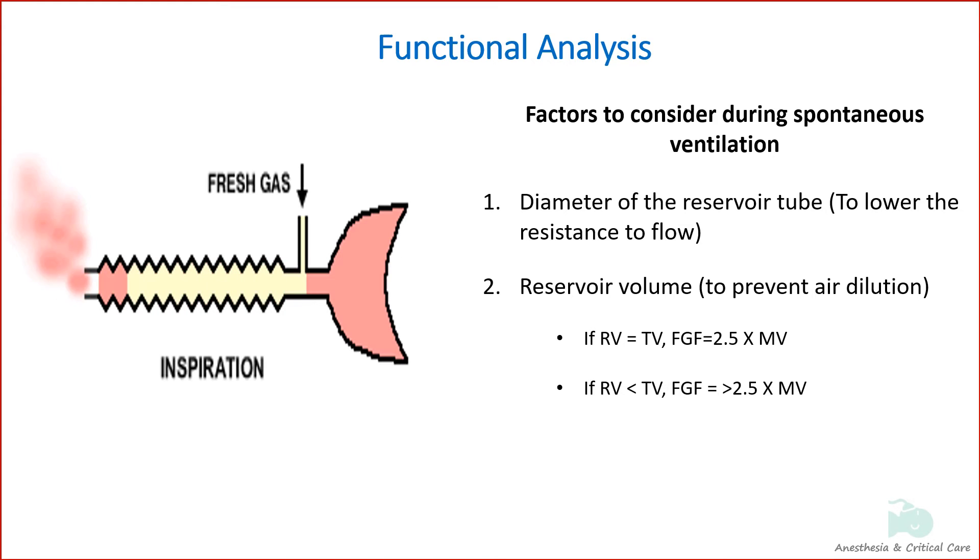If reservoir volume is less than tidal volume, the fresh gas flow has to be increased further otherwise air dilution can occur. If reservoir volume is zero or there is no expiratory limb, the fresh gas flow should be at least equal to the patient's peak inspiratory flow rate to prevent air dilution.